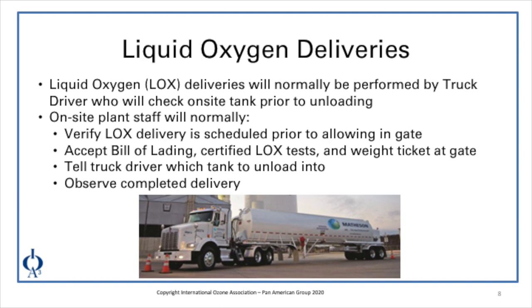Let's talk about liquid oxygen deliveries and some safety elements around these deliveries. Liquid oxygen deliveries will normally be performed by a truck driver who is an employee of an oxygen supply company. That truck driver will park the truck, check the tank, connect hoses as appropriate, open valves, and load the tank. The on-site plant staff will normally verify liquid oxygen delivery as scheduled prior to allowing the truck at the gate, accept the bill of lading, certified LOX tests, and weight tickets at the gate, identify to the truck driver which tank to unload into, and observe the completed deliveries.